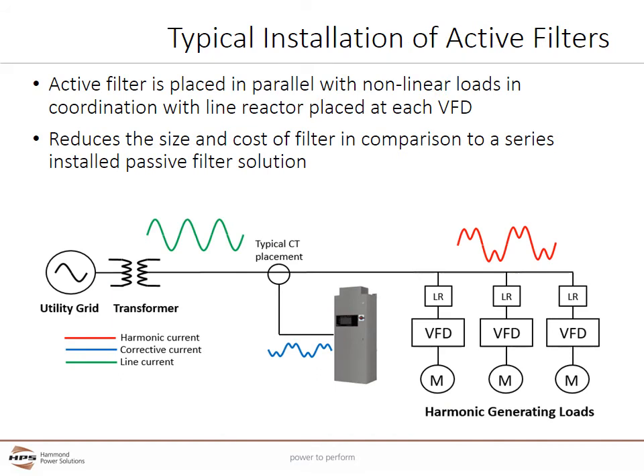An active filter is placed in parallel with nonlinear loads in coordination with line reactors placed at each VFD. This is less costly and more flexible than using series-placed passive filters at each VFD. Line reactors help mitigate a portion of the current harmonics for less cost per amp than an active harmonic filter, but line reactors can't mitigate the current's total harmonic distortion to below 5% — for that, the active harmonic filter is needed. The combination of an active harmonic filter and line reactors is less costly and easier to specify and install versus multiple passive filters, and provides more consistent results over a wider range of loads.